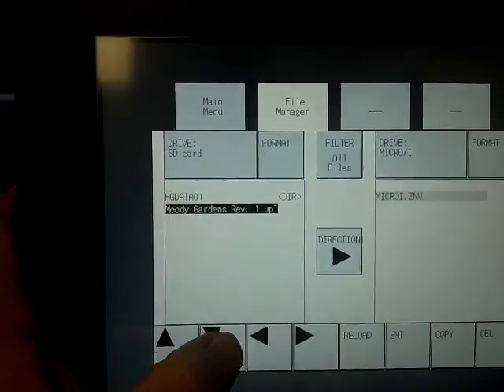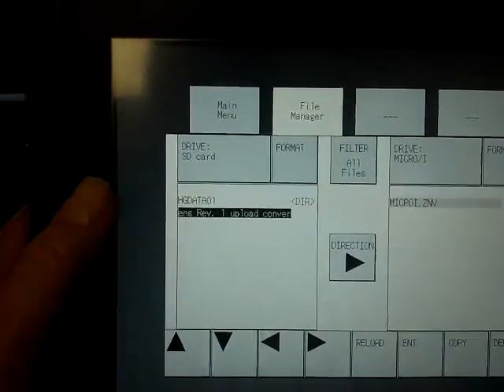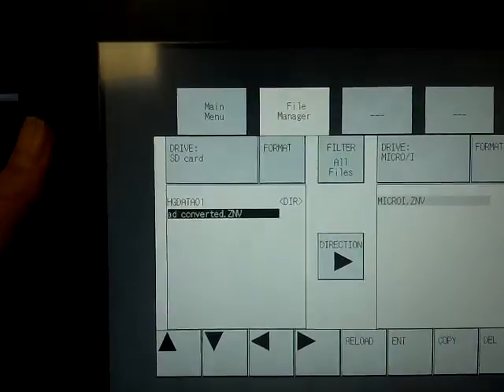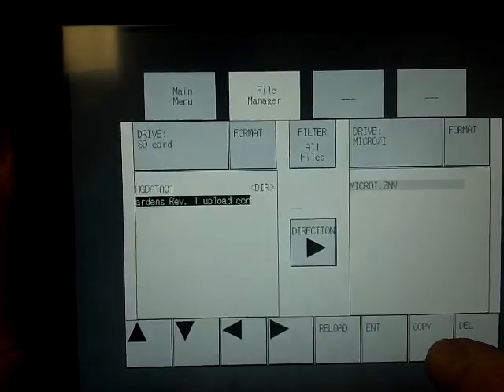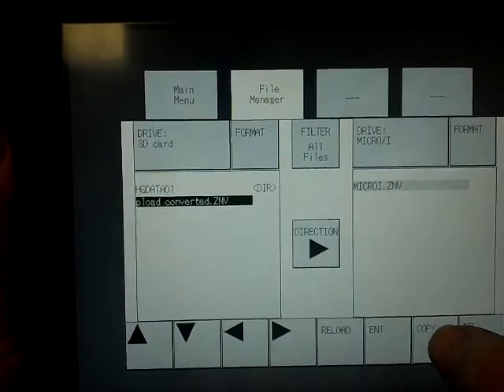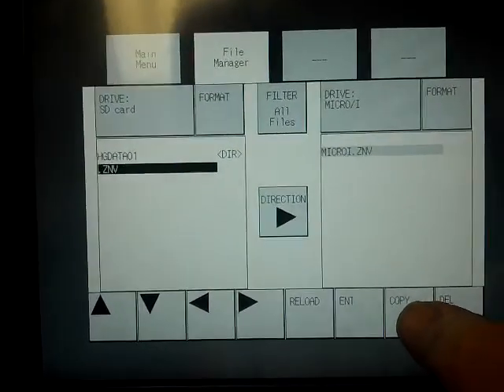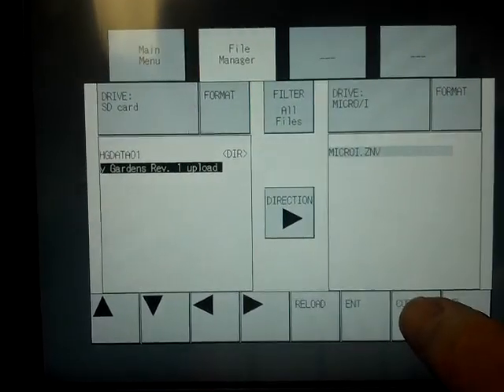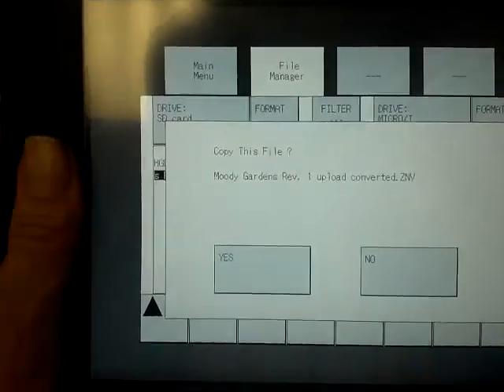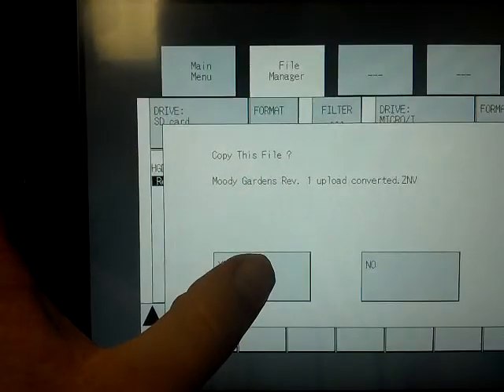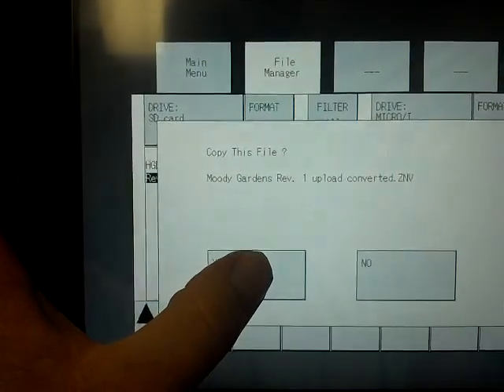We're going to go down and select the program we want to copy. Then we're going to hit the copy button at the bottom. It'll ask you to confirm you want to copy that. Hit yes. Now it is going to overwrite the old program. So if you need to save your old program, make sure you do that prior to starting this transfer, because you will not be able to restore it after this.